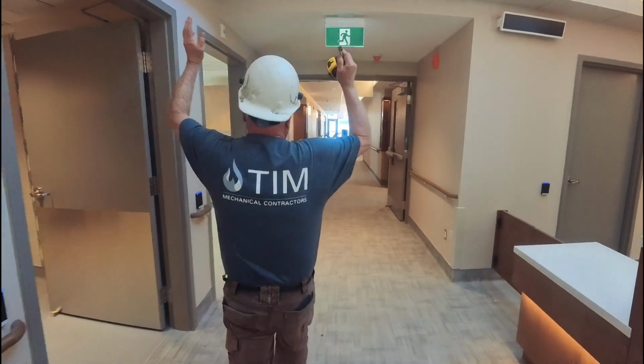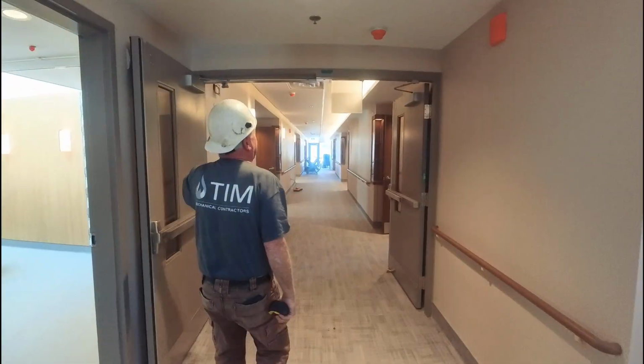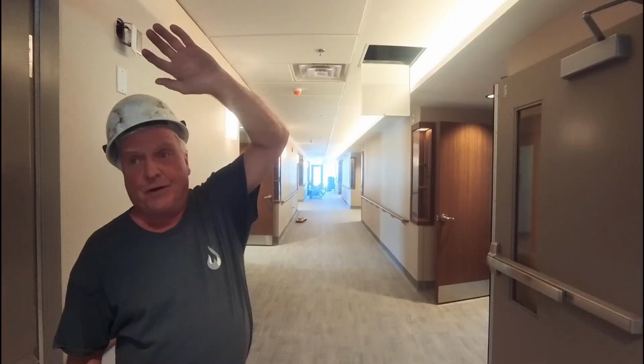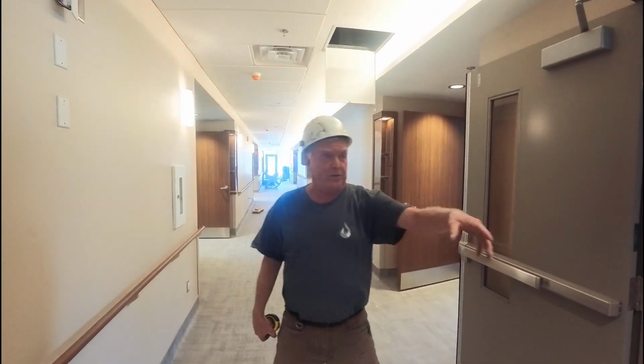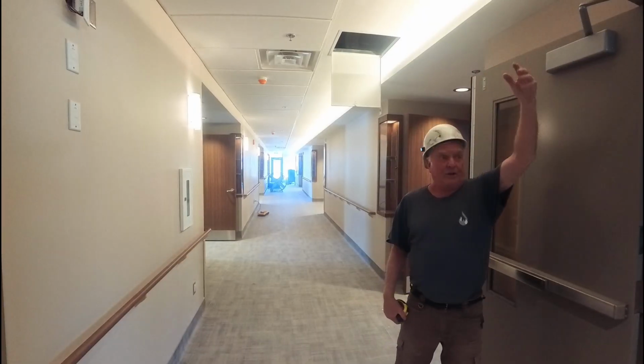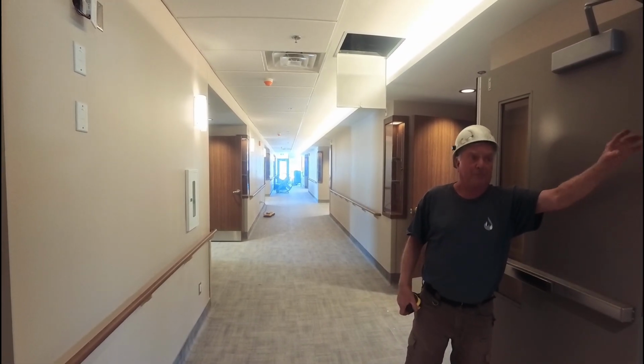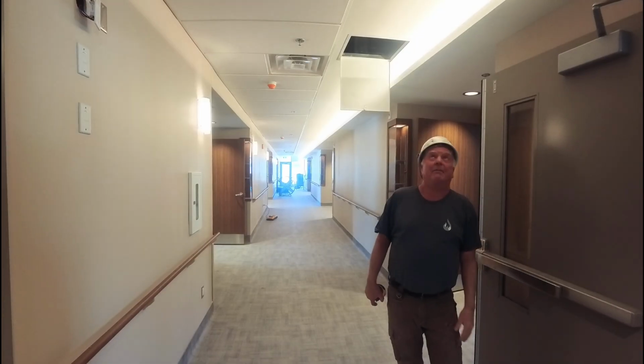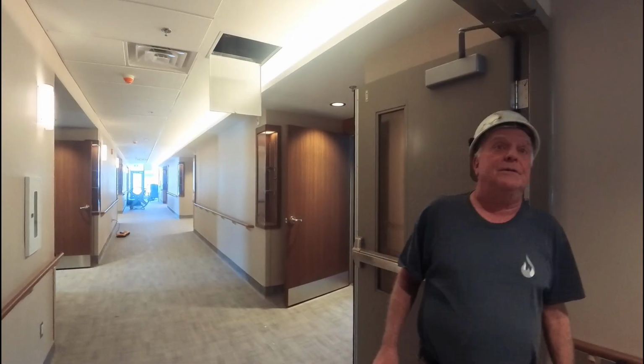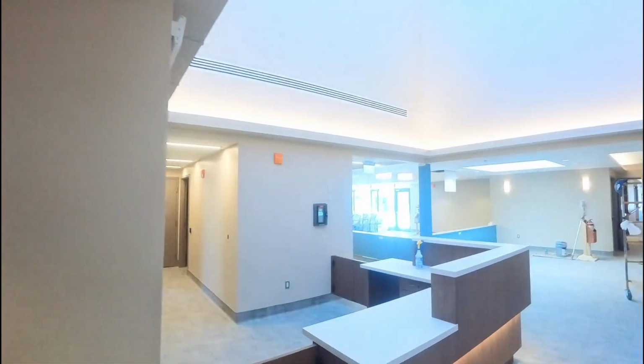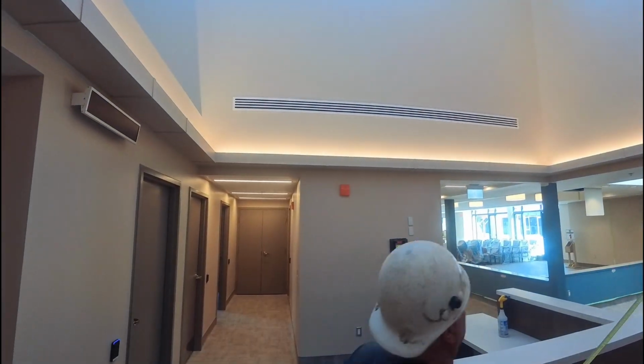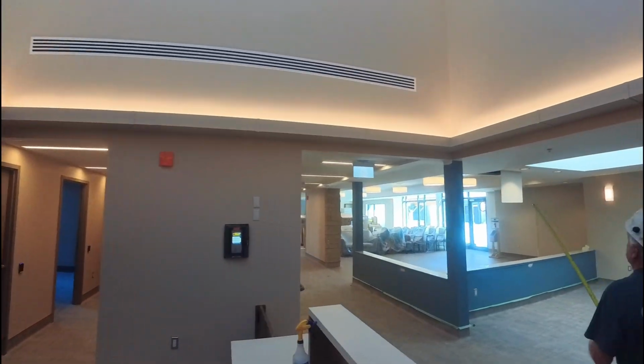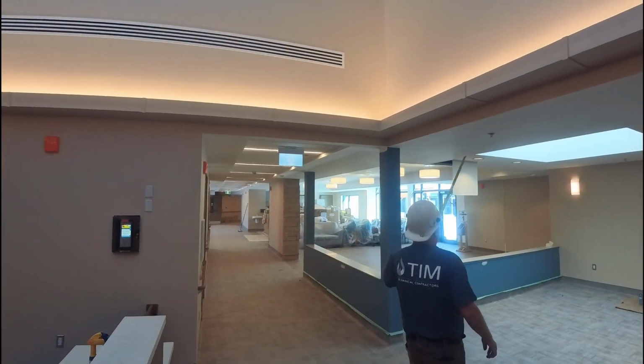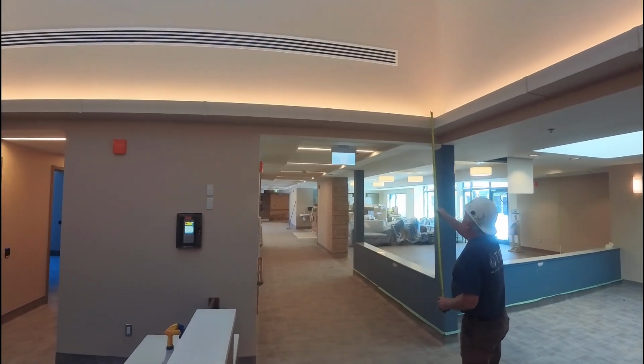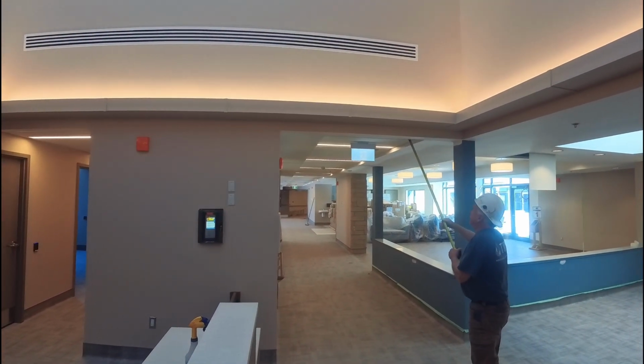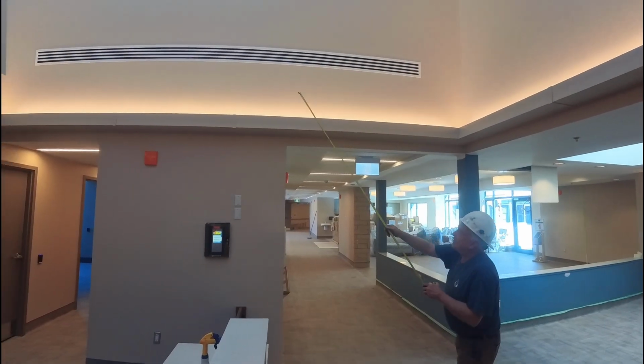As the ducting comes into this hallway, each wing is separated by a fire separation wall. The fire separation has a fire damper that you and I talked about this morning. Yep, how it closes and opens based on the power supplied to the damper itself. Where does this one come from, Dave? That is a supply diffuser that is coming off of this side of the supply duct, the main drop coming through.